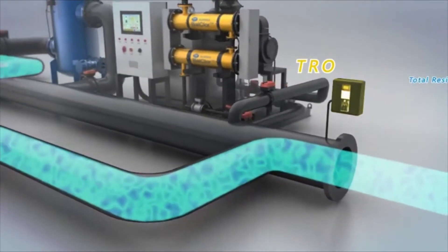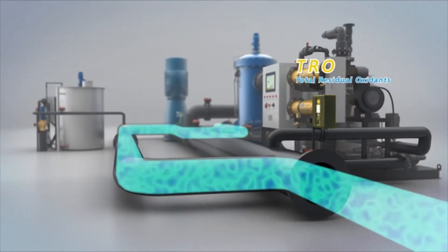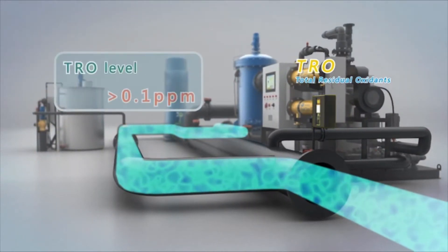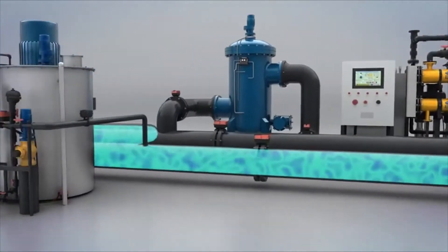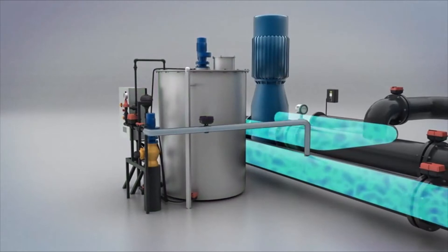TRO, total residual oxidant sensor installed at the outlet of de-ballasting pipe will closely measure the concentration level of active oxidant. If TRO level is higher than 0.1 ppm, neutralization unit will be operated automatically. The neutralizer will be injected into the de-ballasting pipe.